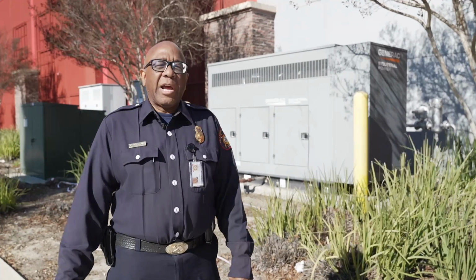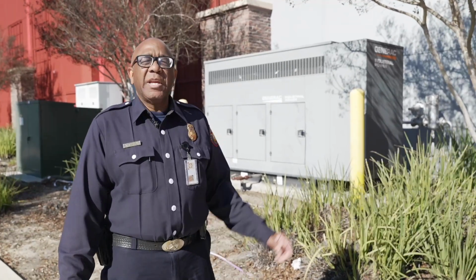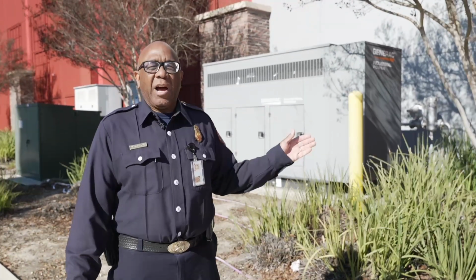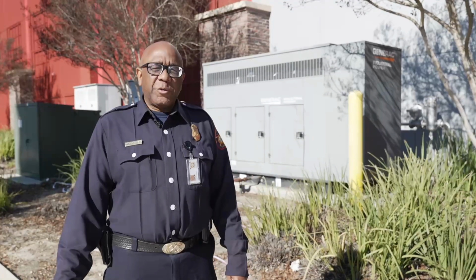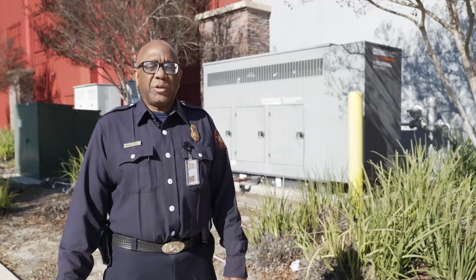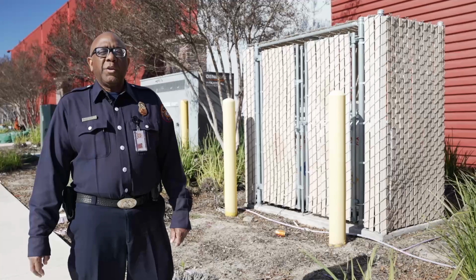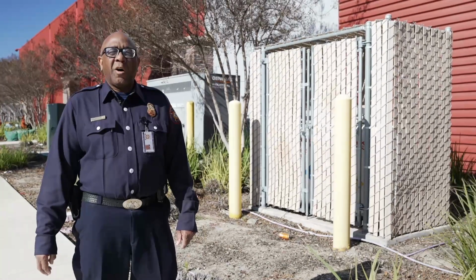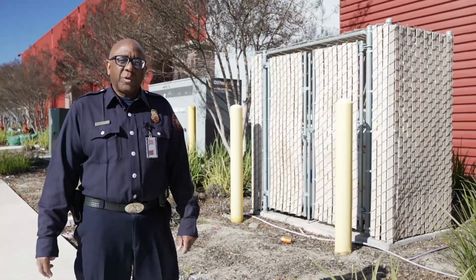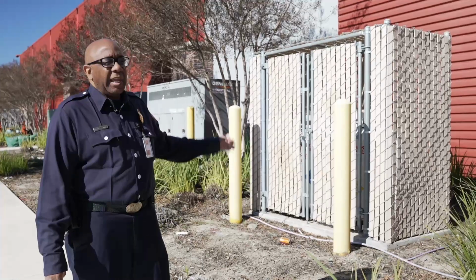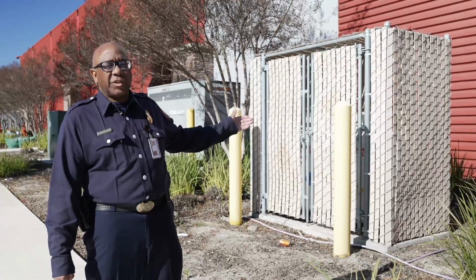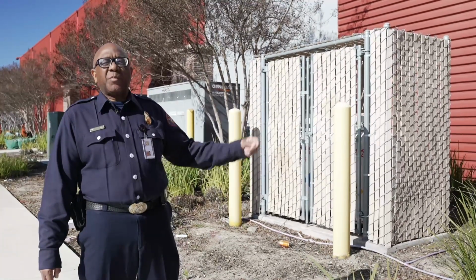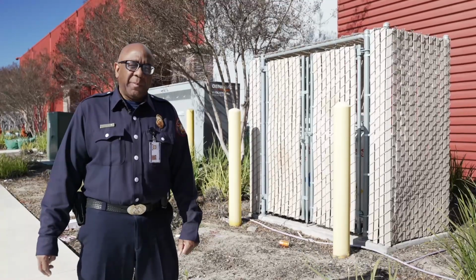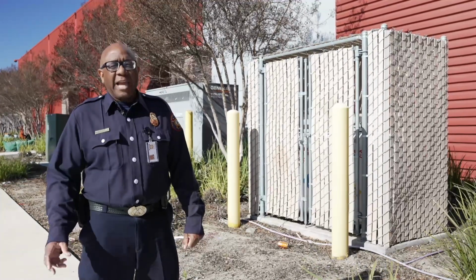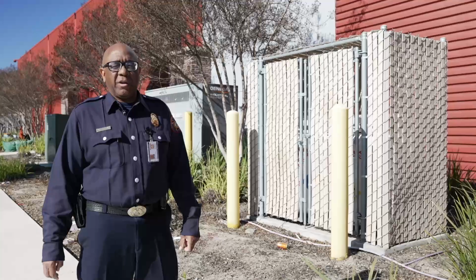Although generators are not required for mercantile occupancies, many of them are installing these now to protect their refrigerated and frozen products from damage during a power outage. Generators can be run on diesel, natural gas, or propane. As you see here, they have a propane installation for their generator. Propane requires an annual permit that's evaluated by the fire department each year.